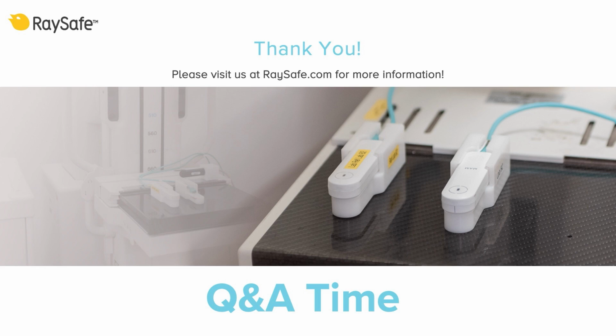Can it easily be cleaned from contamination? Both yes and no. It can easily be cleaned by a damp cloth and a mild detergent, for example, as long as you clean it on the outside of the 452. If you have contamination on the inside of the meter, then it's much, much harder, especially if the GM pancake itself is contaminated. Then in the worst case scenario, if you have contaminated the internals of the GM tube, we might need to actually change the GM tube.